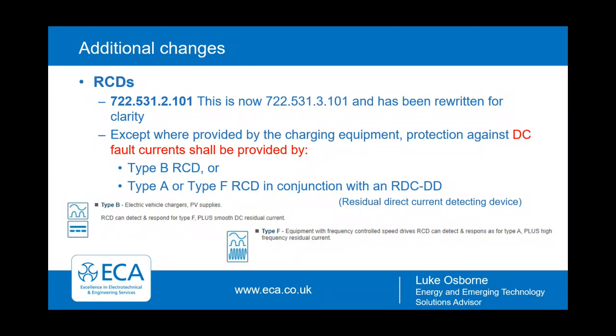So what the hell is an RDC-DD? Essentially, it's for permanently connected AC EV charging stations. So these are your mode threes, which are likely to be put on people's houses and commercial buildings. And the purpose is to remove or initiate the removal of the supply to the electric vehicle in cases where a smooth residual direct current equal to or above 6 milliamps is detected. This can be incorporated as part of the electric vehicle charging equipment.